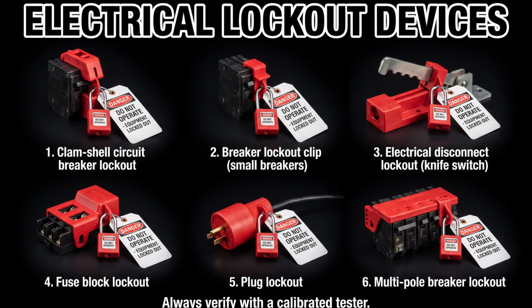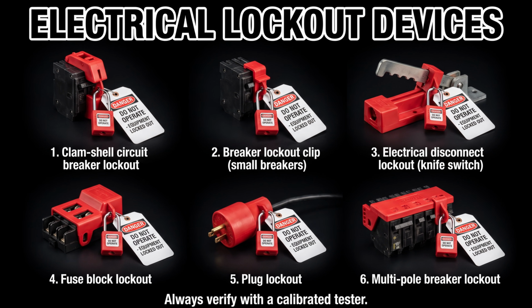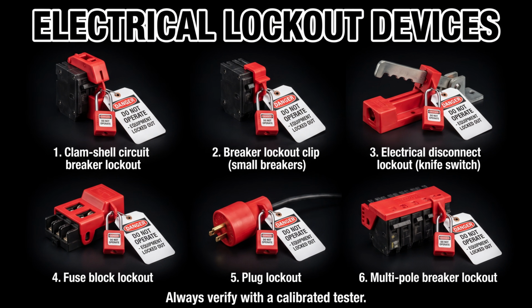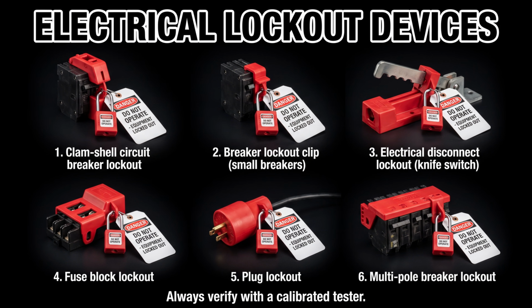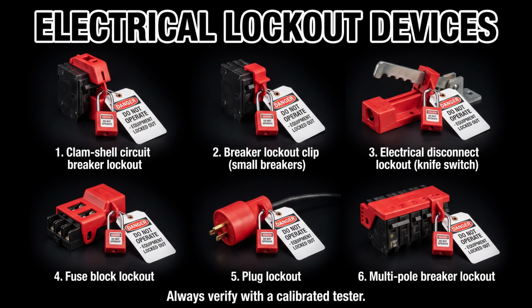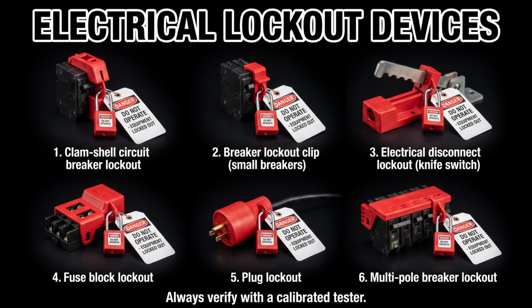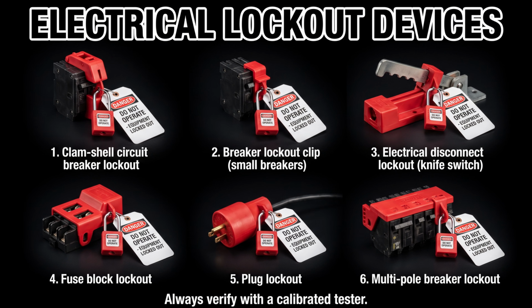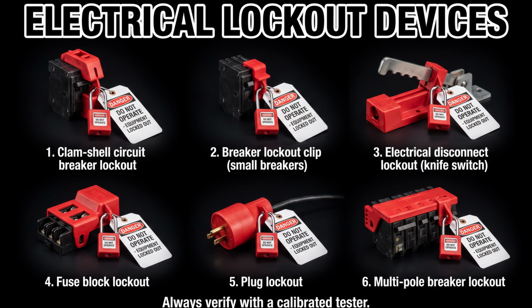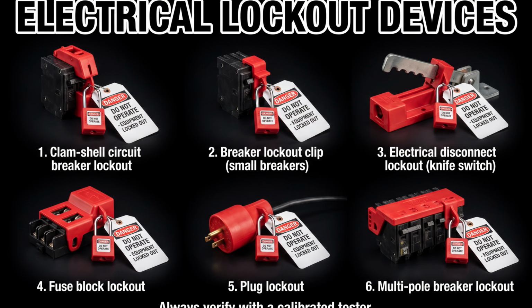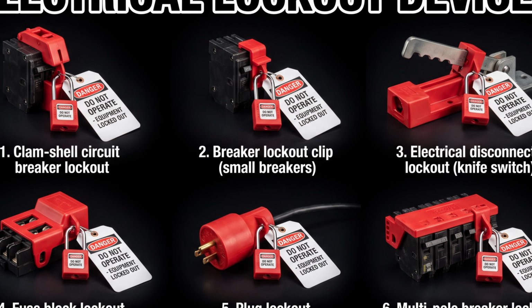Primary lockout devices include clamshell circuit breaker lockouts that enclose the breaker and accept a padlock, electrical disconnect lockouts for knife switch disconnects and pull-out fuse blocks, and plug lockouts for smaller cord-connected equipment. After isolating, you must test with a calibrated non-contact voltage tester. For high-voltage systems, test before touch procedures and proper PPE are mandatory.